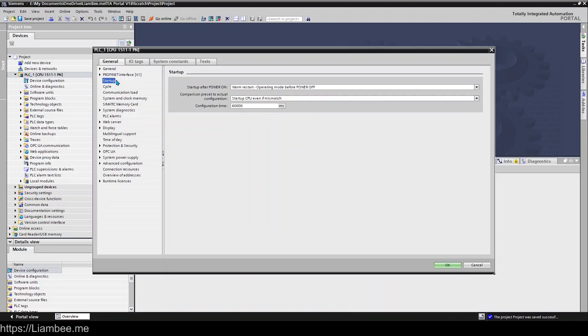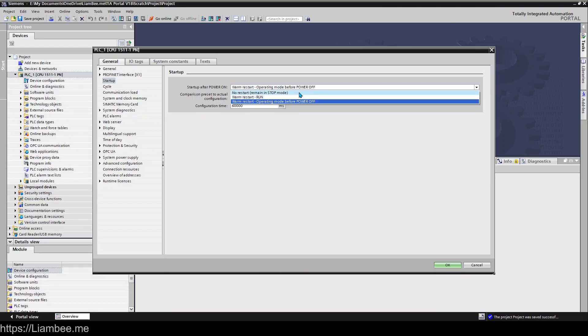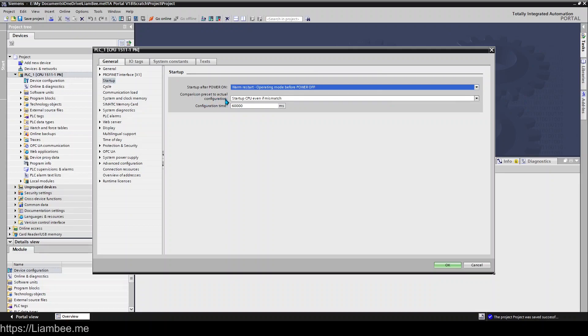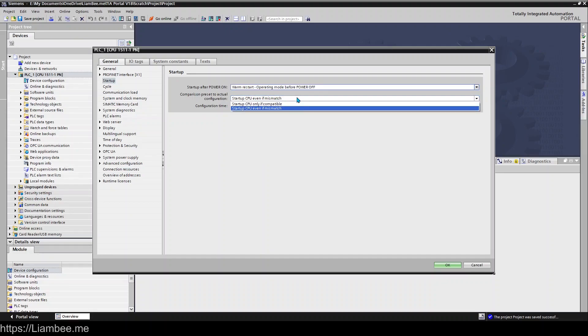Startup you shouldn't really need to touch but there are options to say what you want to do after the power comes back on for your CPU. So you can say be in the same operating mode as before power off run or warm restart and run or say no restart remain in stop mode. You know the power goes off we need our application to be checked if the power went off before the CPU is started. And then we referred to this particular option here about comparison preset to actual configuration when we were setting up output modules for our IO. This is what it refers to here so start up the CPU even if there's a mismatch or start up the CPU only if the output cards or the IO cards are compatible with what the project said they were going to be.